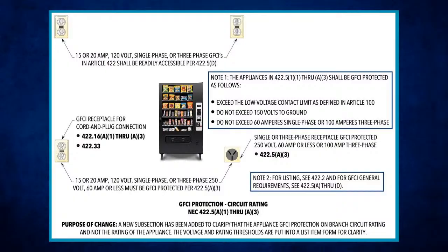To me, this sentence right here, where it says multiple Class A protected devices shall be permitted but shall not be required - if it's internal to any of these listed devices or equipment: automotive vacuum machines, drinking coolers, cord and plug connected high pressure spray washing machines, tire inflation machines, vending machines, sump pumps, and dishwashers - if any of those have internal protection, no, you don't need it.